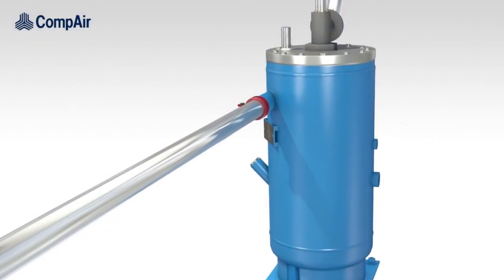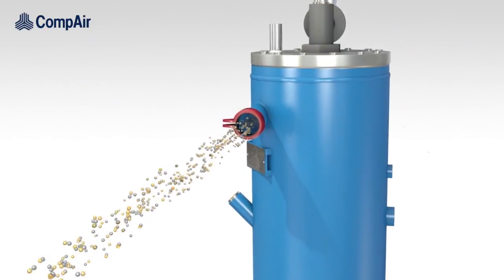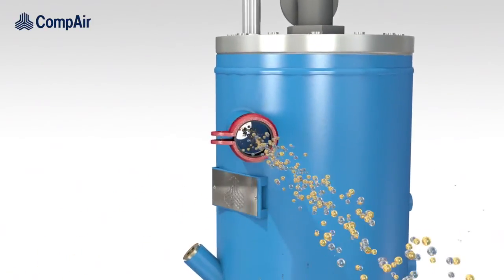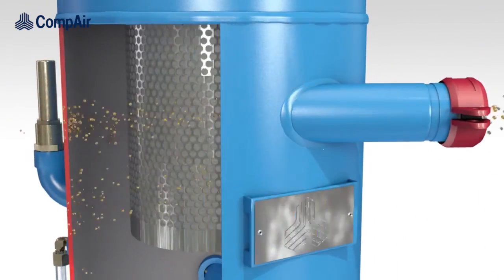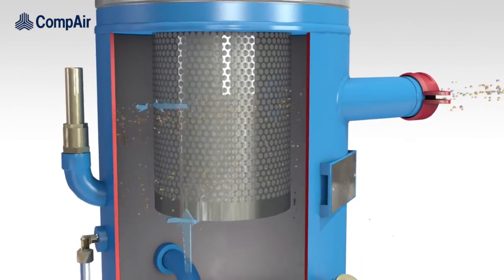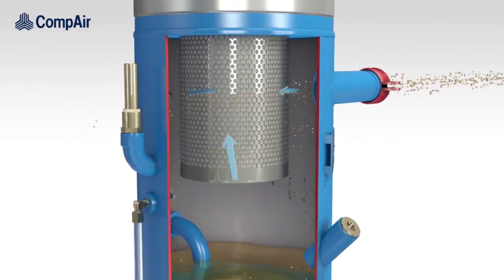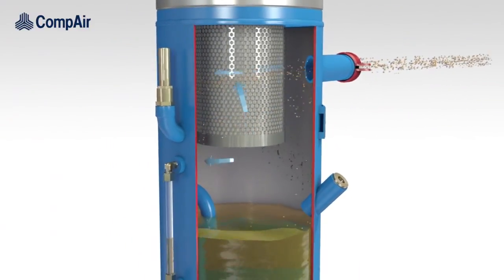The second component is the air oil separator which removes the majority of the oil from the air. The compressed air containing oil is directed into the oil reservoir and rotates around the air oil separator. This cyclone effect provides the initial air oil separation.